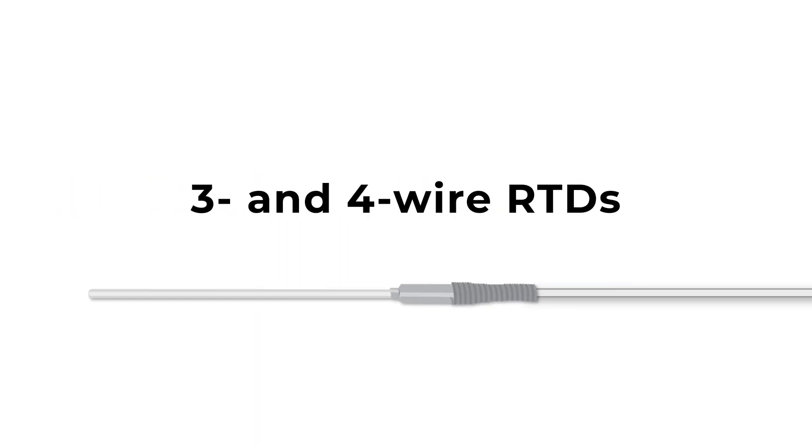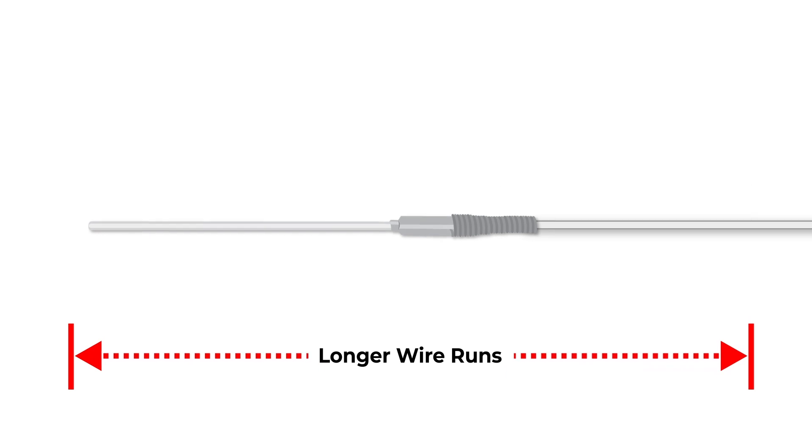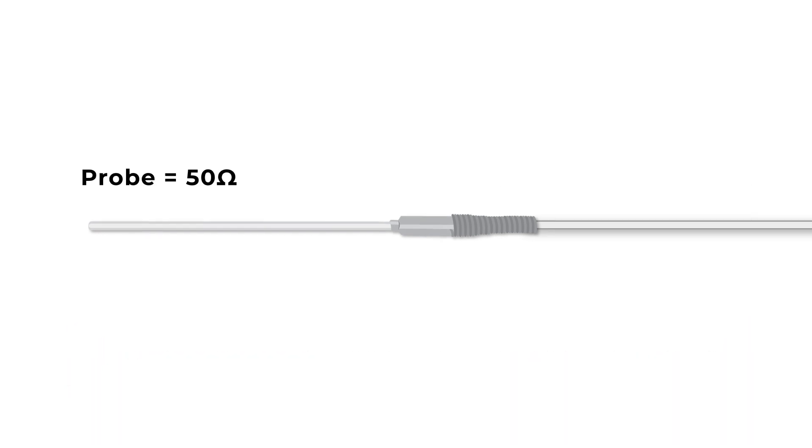Meanwhile, 3- and 4-wire RTDs can have longer wire runs, since they can both differentiate between the resistance of the probe versus the resistance of the wire run.